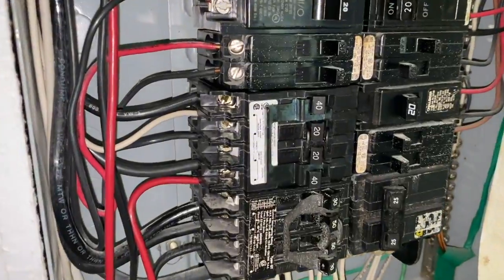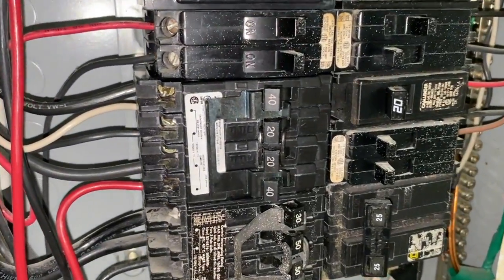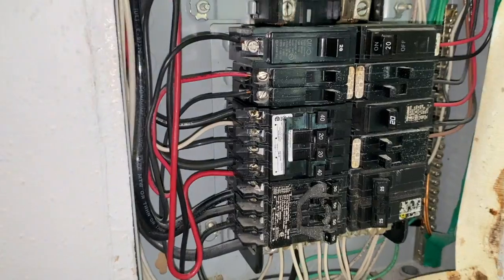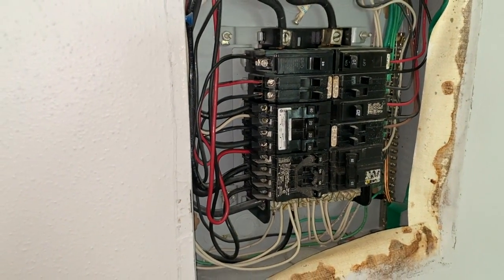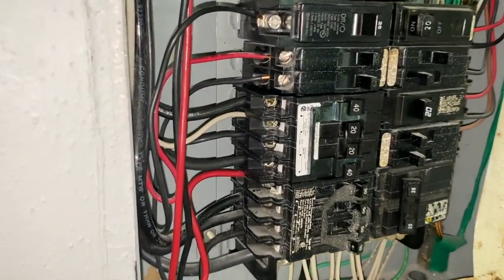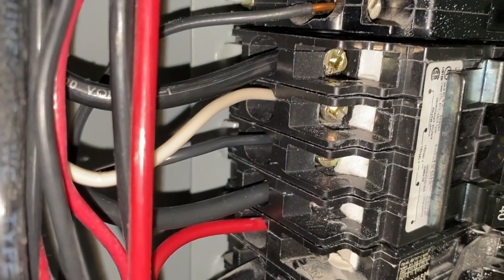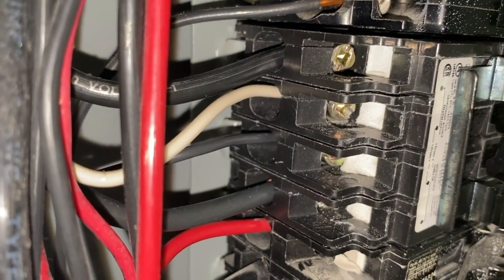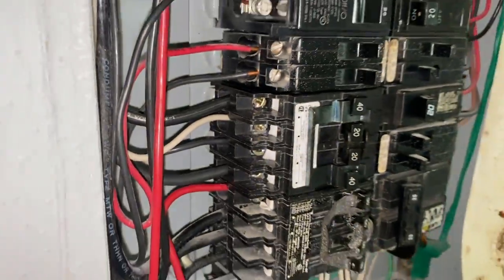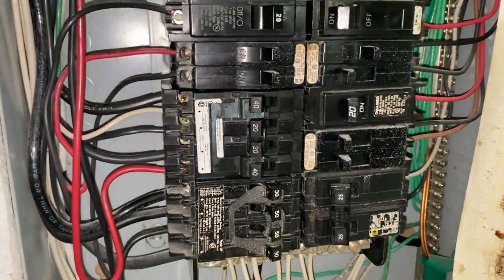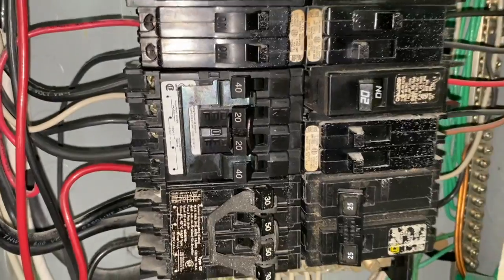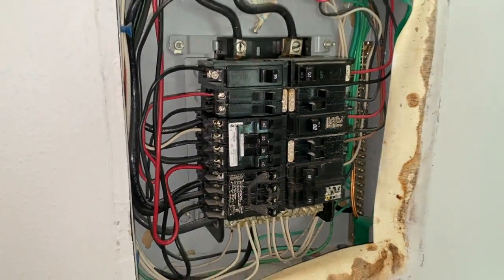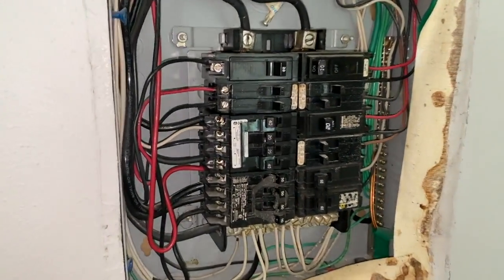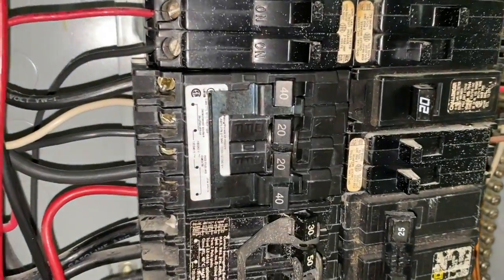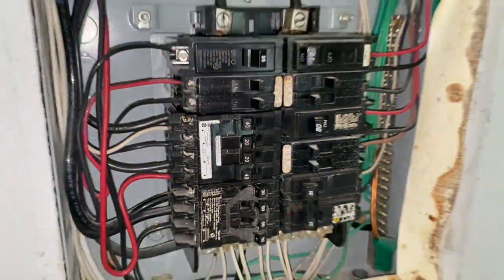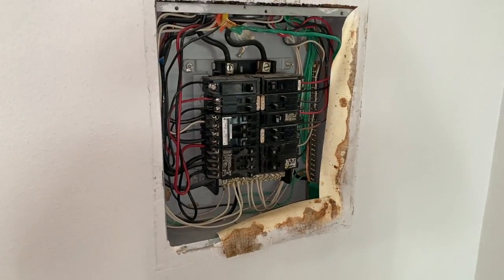Now to a close-up view, and the entire 4-pole circuit breaker has been installed, and DIYers, it is extremely important before moving on and restoring power to your home. Double check everything. And that includes the wires inserted into their respective areas and secured snug with these screws. The breaker itself is positioned properly and locked in place on the inner bus and hooks. And again, just double check everything. We are going to leave both 40 and inner 20s in the off configuration. We are heading back outside to restore power.